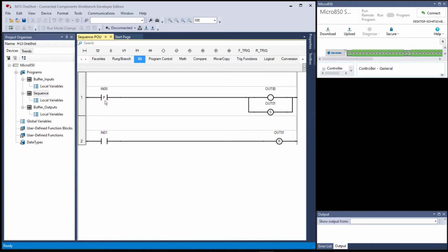Now I realize that because this is a true if on, it kind of goes hand in hand with when this is on and when it's off. But try to keep that out of your thinking. This instruction goes true when whatever in memory that it reads goes on. This particular instruction will only be true for that one program scan when it first detects that that memory location went from off to on. That's because it's a true if on instruction that's pulse rising edge.